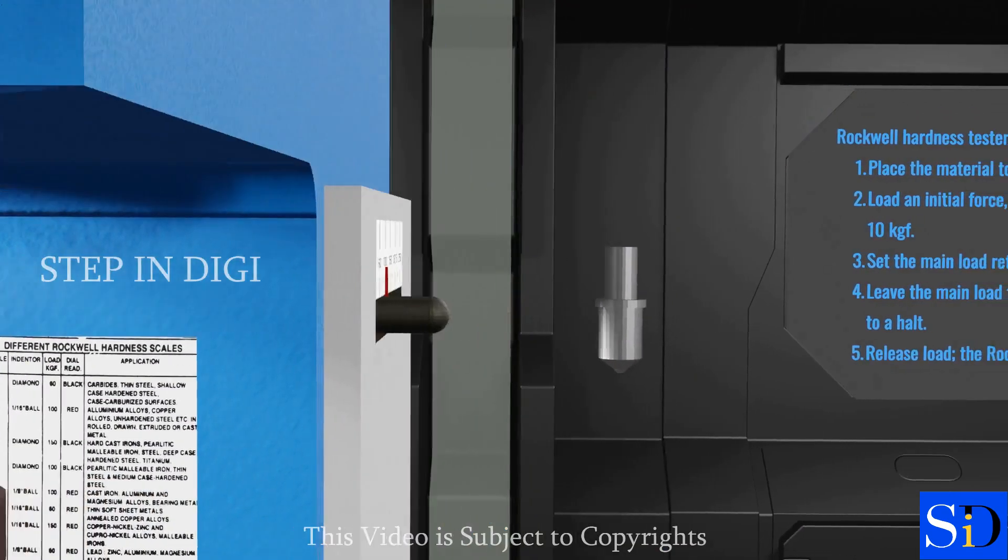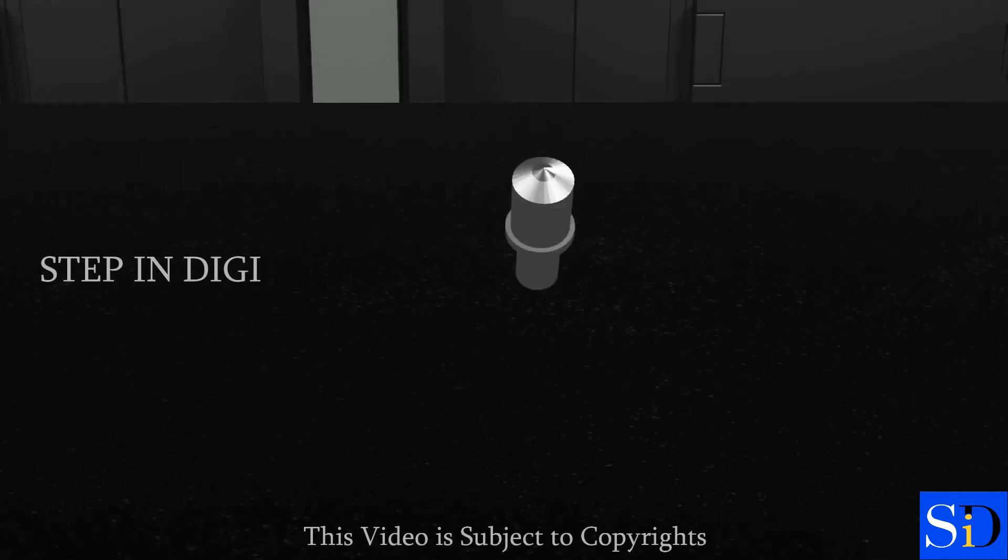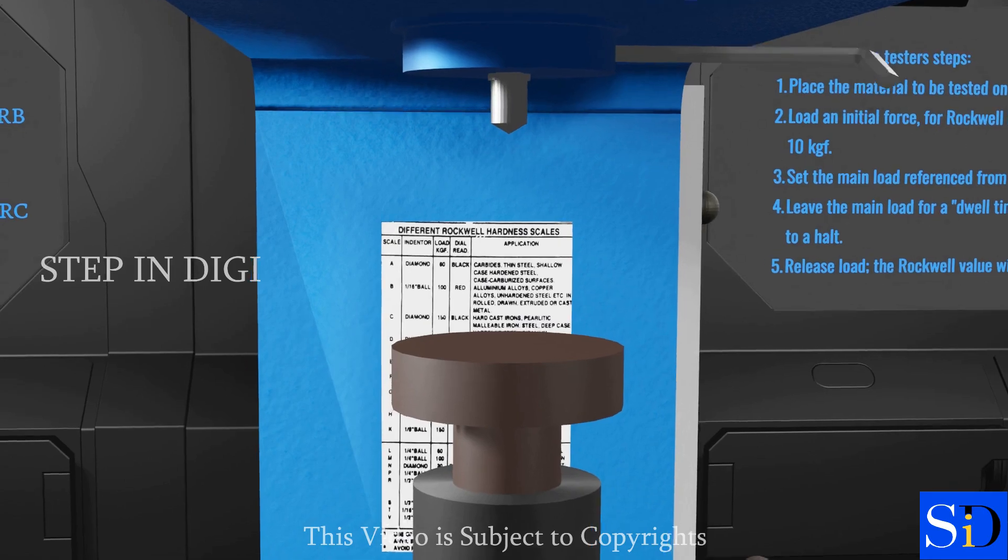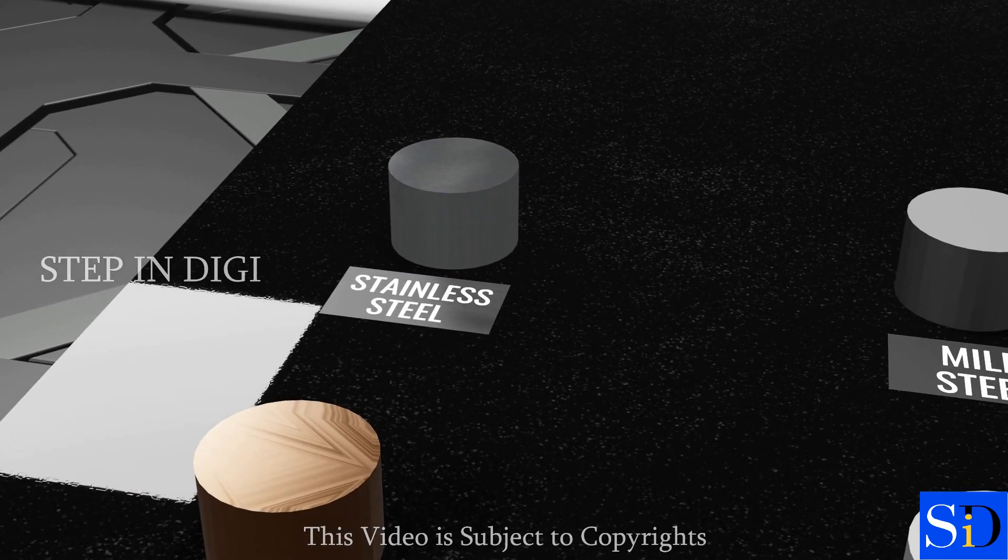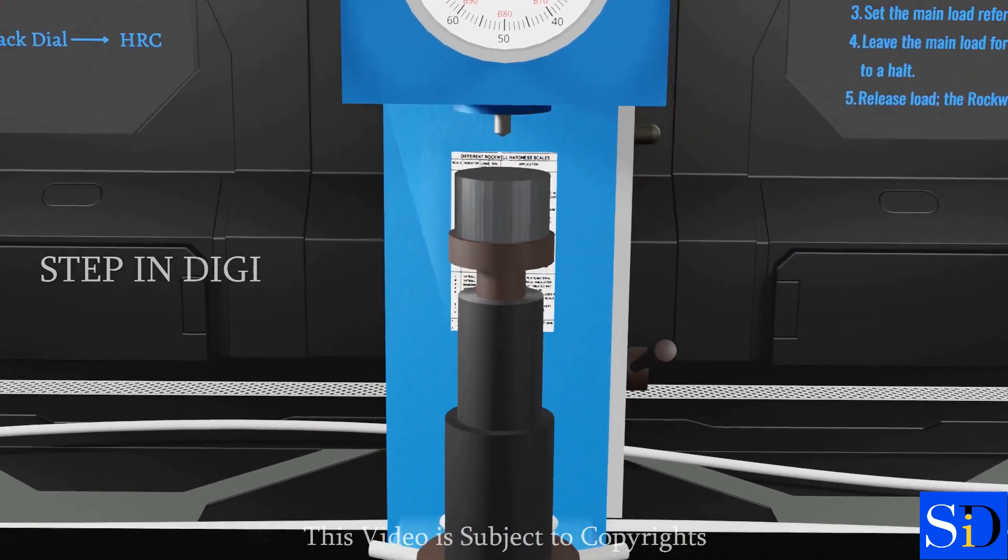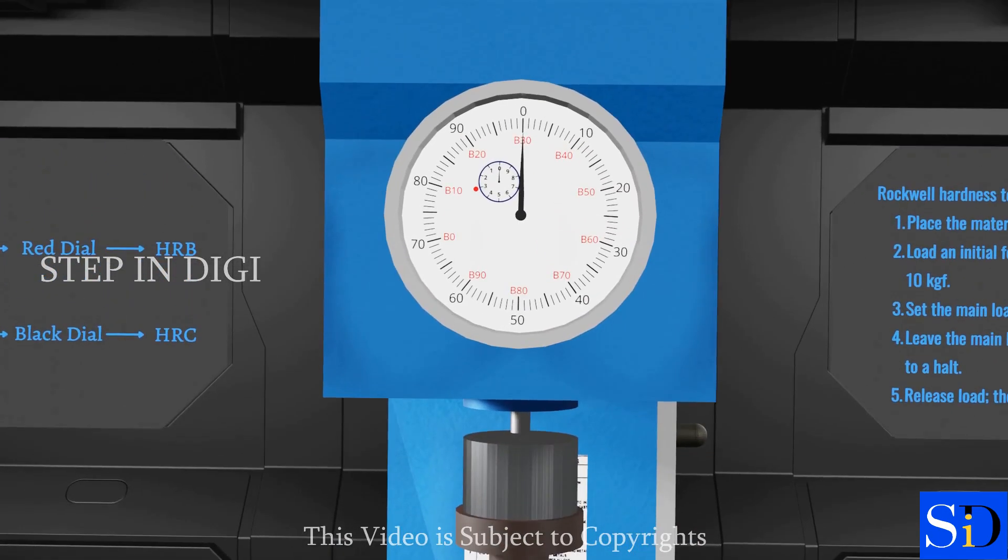First, let's replace the ball indenter with the diamond indenter. Now, let's place the test piece of stainless steel on the supporting table. Now, rotate the hand wheel until the tip of the diamond indenter touches the test piece. And the dial reaches zero on black dial with the bigger needle, and three on the smaller needle, which means 10 kilograms of minor load is applied on the test piece.